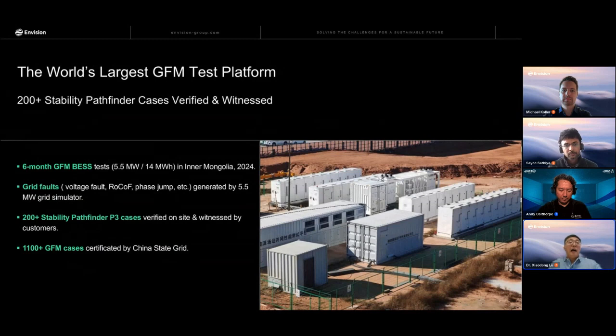So after the design and the investigation of the specifications, and also verification by using the hardware in loop and simulation, here is what we tested on site. We built the largest grid forming test platform. It is a 5.5 MW PCS set, including 2 PCS in parallel. And there's also a battery pack of 14 megawatt hours connected on the DC side. The whole setup was built in Inner Mongolia. And the grid fault is generated by using a grid simulator.